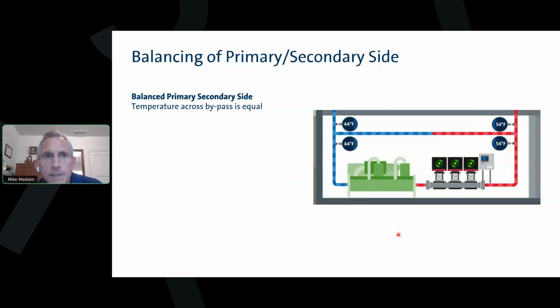And then the decoupler is pretty interesting. So this also helps with our delta T control. And I'll talk through how the decoupler works. So we put 4 temperature sensors, 2 on each side of the decoupler. So here's my chilled water supply. I'm sending 44 °F water out to the system, and I'm sending return delta T 54. When everything's in balance, so when my primary loop and my secondary loop are equal, there's no flow on that decoupler. Let's say you had 10 air handlers running out here in the system and half of them turn off.